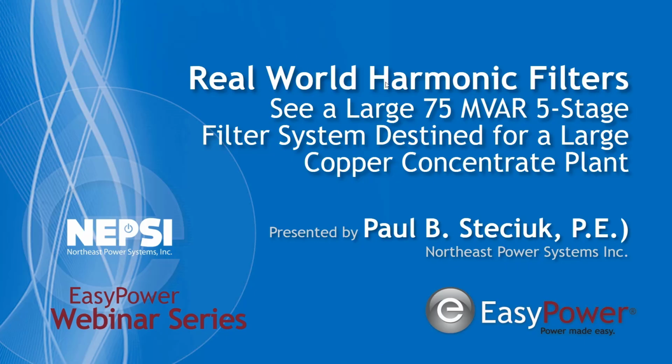Today we're going to talk about a real world harmonic filter that we have designed and built here at Northeast Power Systems. We actually built 3 of these systems, each one rated 75 megavars, 5 stages at 38 kV. We're going to do a deep dive into this harmonic filter system. It's destined for a copper concentrate plant, and we will teach a little bit about what a copper concentrate plant is, the type of loads that exist at those types of facilities, and the type of harmonic filters that we have provided in the past to those types of systems.